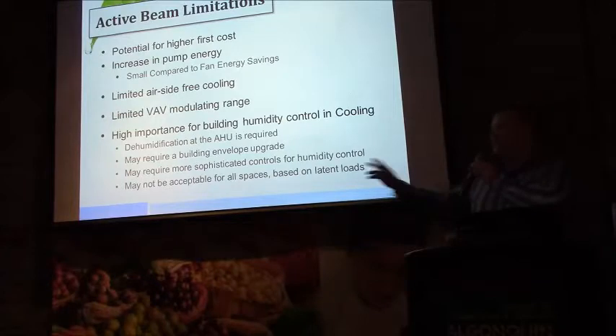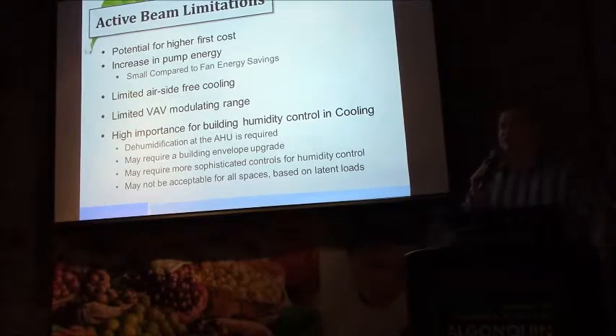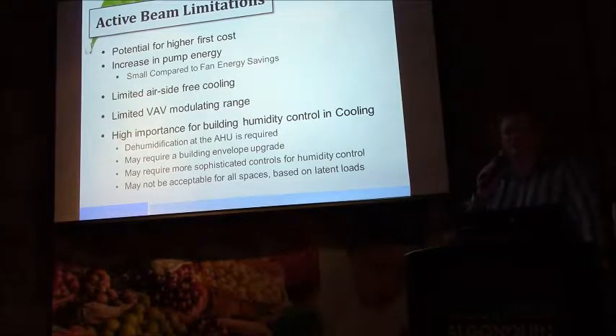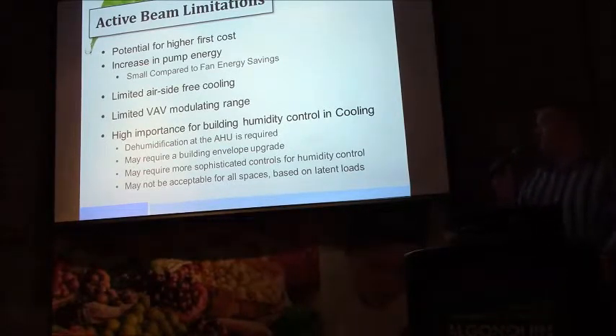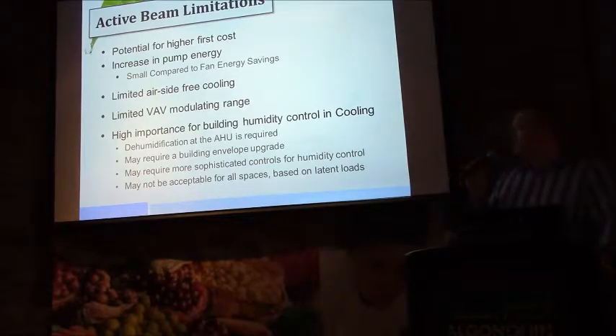We may need more sophisticated controls for humidity control. Conceivably, at every zone, we would want to have some level of feedback to ensure that the space hasn't fallen out of design, or that if it has, we've had some means to respond to that, be it turn off the chilled water to the zone completely, or reset the zone in the event that it's a larger application.